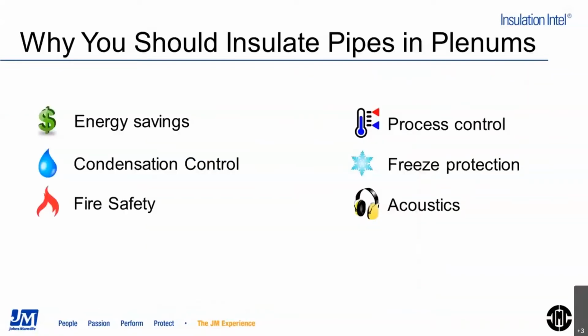So as in any situation, you should be insulating pipes in the plenum or otherwise, because insulation provides a number of benefits, and they are listed here. So it provides energy savings, process control. So if you are transferring cold or hot fluids through the plenum, you want to make sure that those fluids arrive at the correct temperature to where you need to use them. So related to the cold fluids, you would want to keep them cold and prevent condensation. Condensation can cause issues with just dripping water. And again, we do have electrical conduits and things like that. And if the condensation is not controlled, you can also have mold and fungi growth in the plenum space.